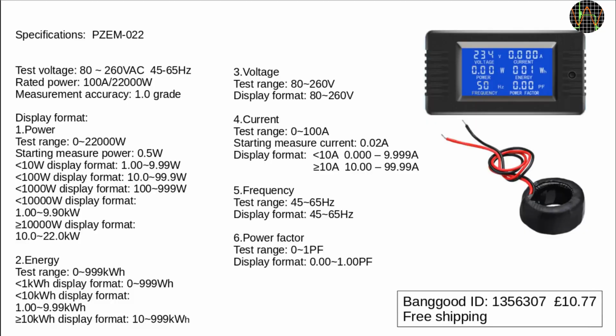A summary of the datasheet shows that the module is rated for 80 to 260 volts AC and up to 100 amps or 22 kilowatts, which is of course an overkill for my purpose, but it could be interesting for people with large solar converters. But just to be clear, this module works only with AC. It does auto ranging on current, power and energy readouts. The lowest power value is 0.5 watts and the lowest current is 20 milliamps.